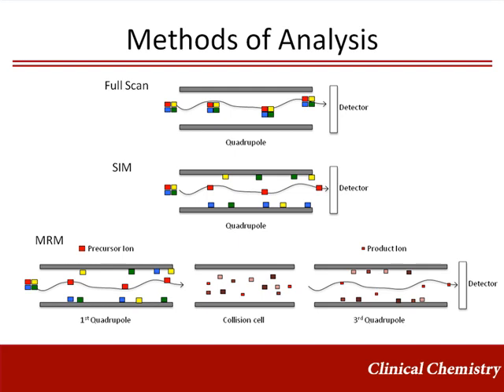Multiple reaction monitoring, or MRM, is used with tandem mass spectrometry. Similar to SIM, the analytes of interest are known, and optimized voltage and frequency settings are determined for both precursor and resultant products. The specificity is enhanced with MRM because of the fragmentation that occurs prior to detection. Though analytes may often share the same molecular weight, it is less likely they will also share the same fragments. Using MRM, precursor ions with identical mass-to-charge ratios can easily be distinguished when unique product ions can be found.